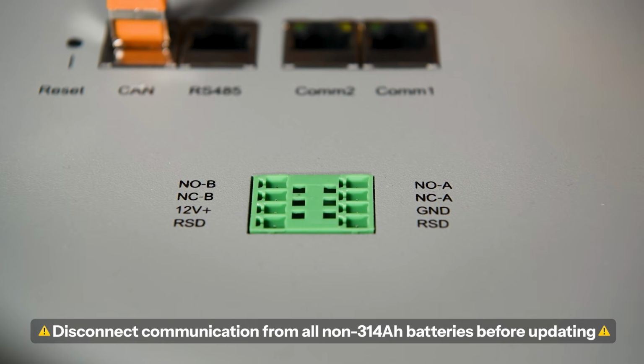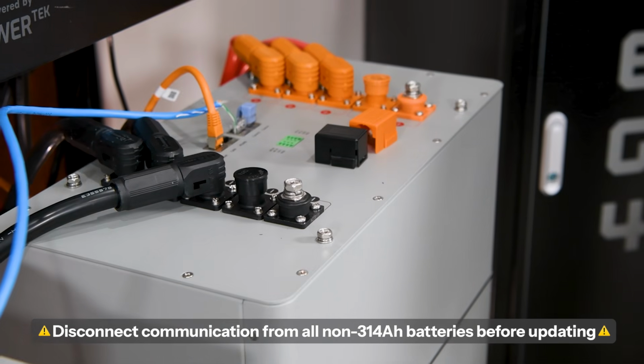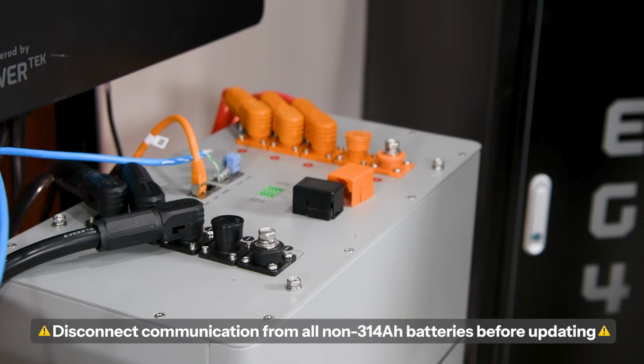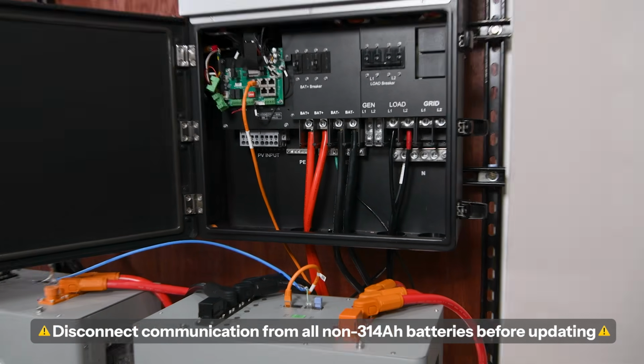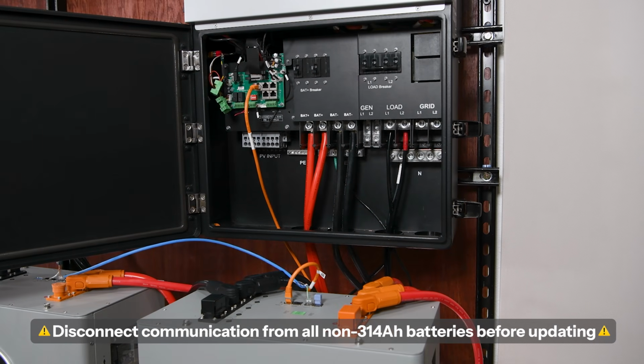There's also one safety step from EG4 that you don't want to skip. Before starting the update, all dry contact connections need to be disconnected from the battery. During the update process, connected dry contact equipment can rapidly change state, which can lead to unintended behavior or equipment damage. With those items checked off, we're ready to move into the EG4 Monitor Center and start the update process.